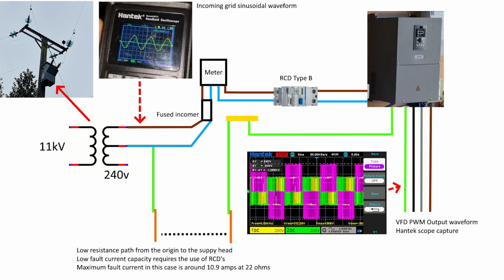Our new factory has a TT electrical installation. There are a few main types of these, and they matter quite a bit for this application and must be understood. In this schematic, you can see there are 2 phases coming from the substation on the existing transmission line. These will be at around 11 kV and they go into a step-down transformer on the pole. They look like the one shown here in the schematic. This reduces the voltage to around 240 volts and provides us with a neutral and an L1 connection. This is also commonly referred to as the live or hot conductor in America.